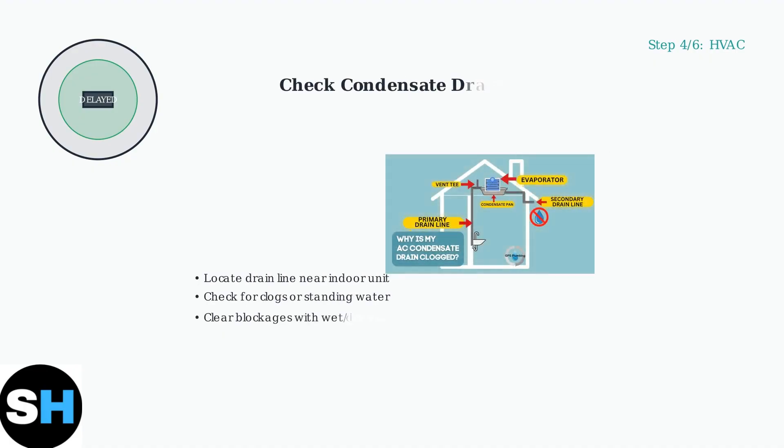Step four, inspect your HVAC system. Start by checking your air filter. A dirty filter restricts airflow and can cause system delays. Also check your condensate drain. A clogged drain can cause your system to shut down and display delayed messages.